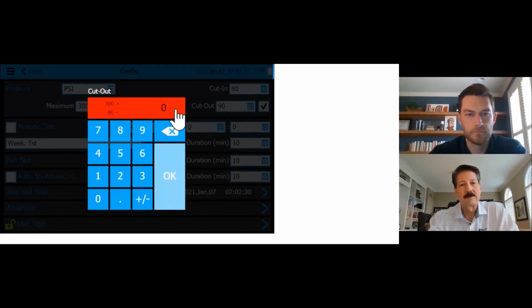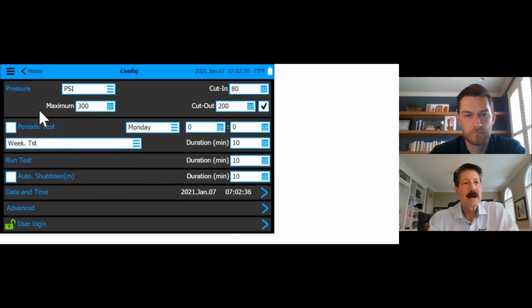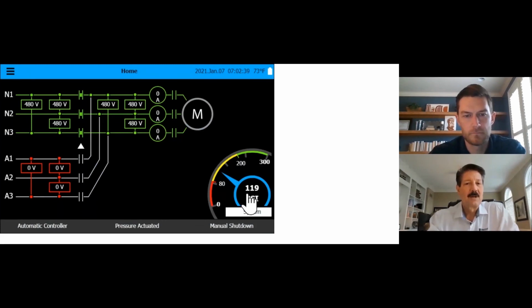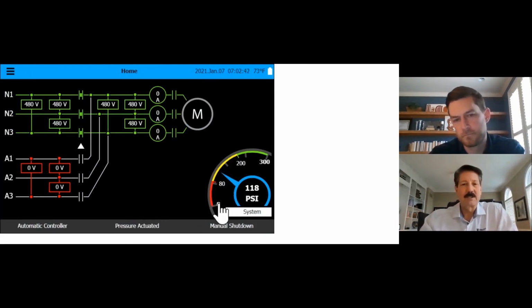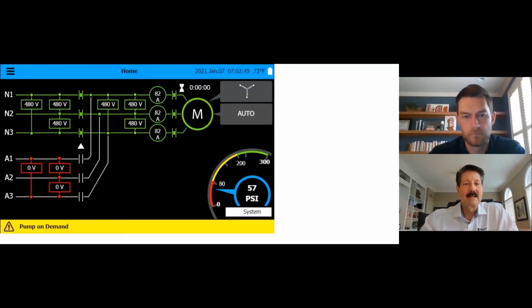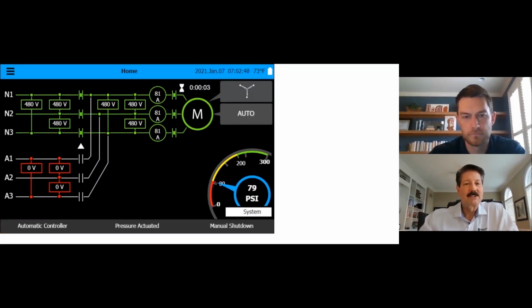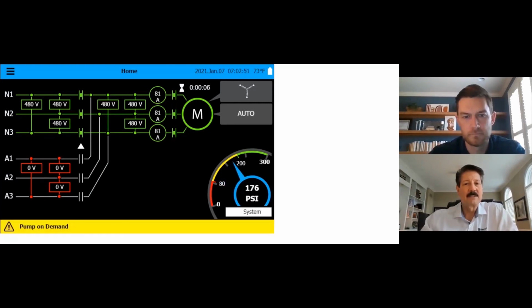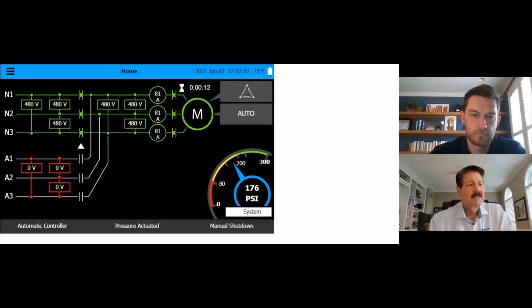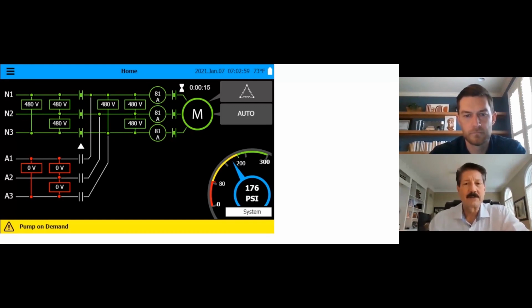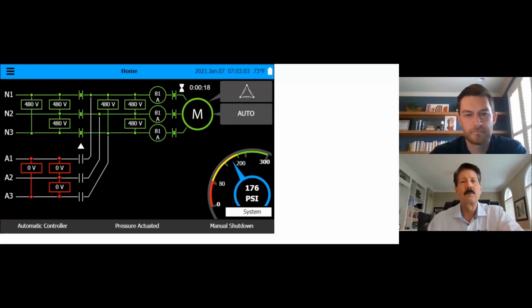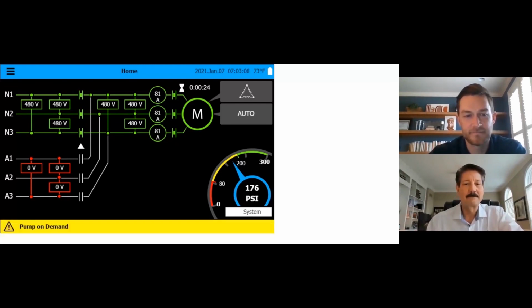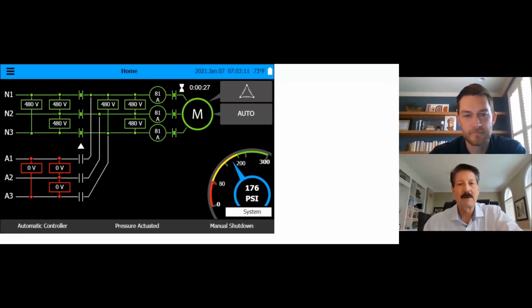And here's something that I found a few people have done. I had someone who actually put the cutout pressure very high up. So even though the cut-in was at 80, and we have a pump on demand, the system pressure came up and came up and came up, and all of a sudden, the system pressure couldn't deliver any more than roughly 175 or 176 PSI. The gentleman, I asked it, he goes, "Oh no, we just shut it off with the flange-mounted on-off switch." I go, "Well, I have a simpler thing to do here," because even when you manually shut this off, you have to have the system pressure above that cutout point.